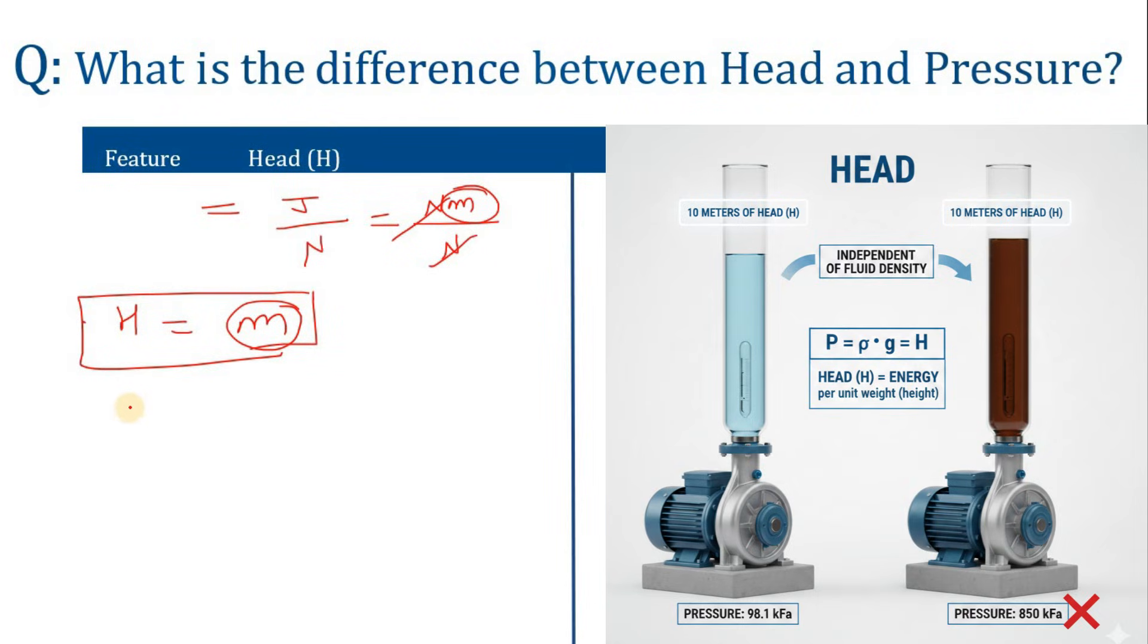It means that let's suppose you have one pump, and I am saying that the head of this pump is 40 meters. So what is the meaning of that 40 meters? It means that a pump can lift any fluid, whether it is water or oil or hydrocarbon, any fluid. That pump can lift 40 meters irrespective of any fluid you are using. That is the meaning of the head, that is the meaning of independent of density.